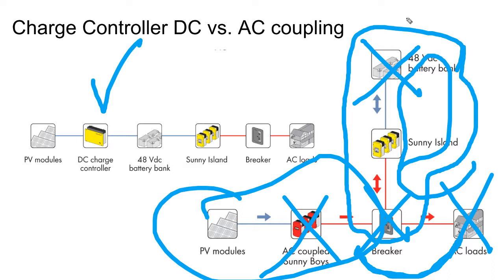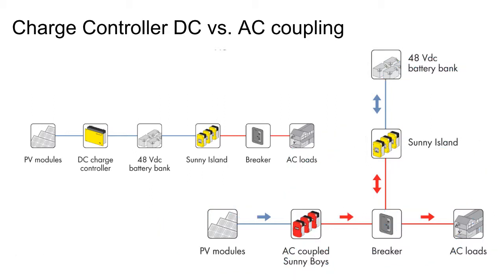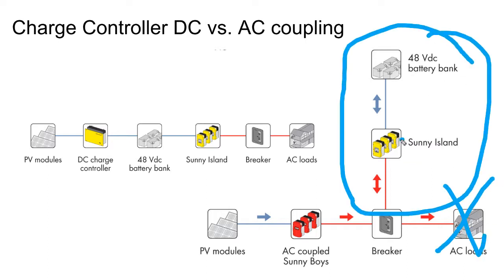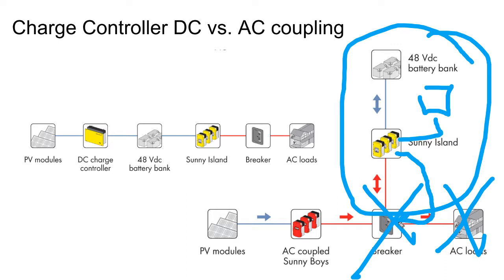You say, well, can't the battery inverter turn the solar array back on? And the answer is, well, it can, but A, the manufacturer may not support it. Like in SolarEdge's case, they say, we're not rating our system for off-grid. If you're doing any kind of backup power because of the grid failure, it needs to be on a dedicated critical load panel, and that's it. We're not going to allow you to supply your whole house breaker panel. And while you could do that little cheat that we looked at earlier in the program, where you're tying into the top of the bus bar, that voids your warranty, and that's not something the manufacturer is even going to tell you that you can do.